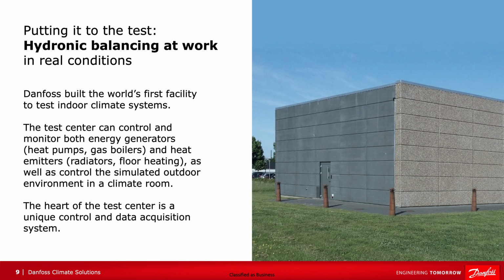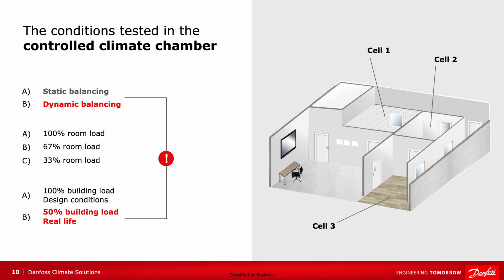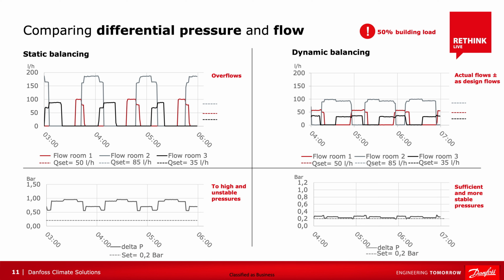The conditions we tested in this climate control chamber included some static balancing and some dynamic balancing, to prove the benefits at different loads in different rooms and different conditions, as we can see here. When we compare differential pressure and flow, and once again, back to the hose, you can see on the static balancing we have big spikes of flow and pressure. It looks like driving over moguls or a bunch of speed bumps. With dynamic balancing, it's a much smoother surface, a much more consistent flow and pressure across a wide range of conditions.